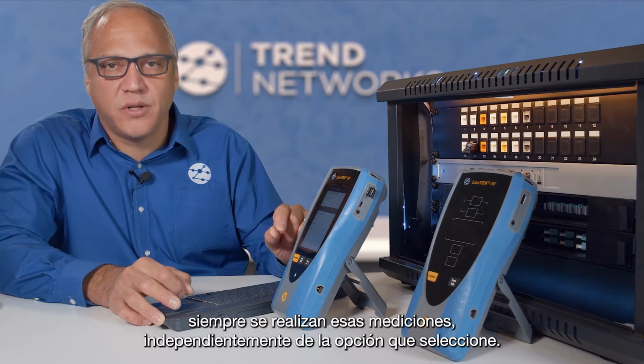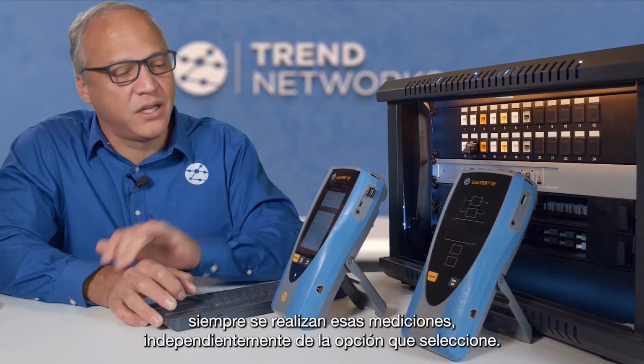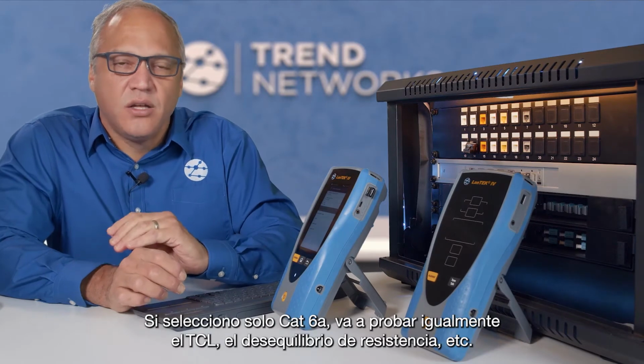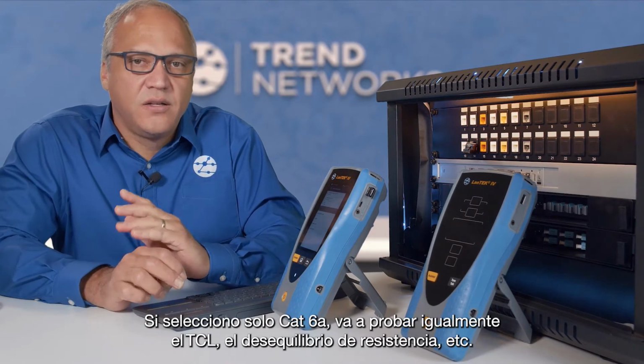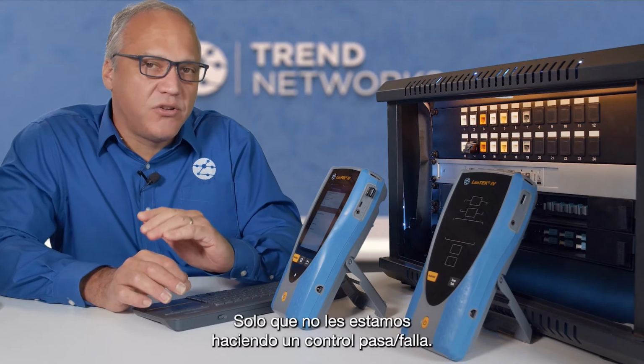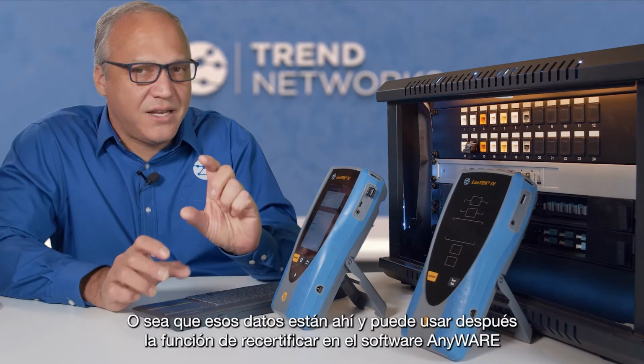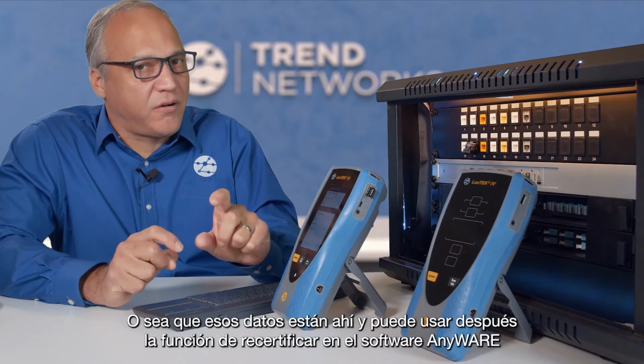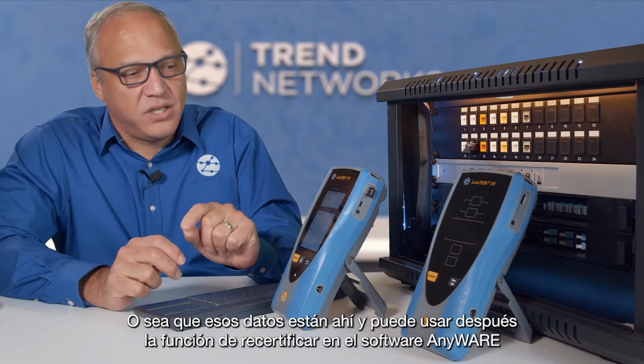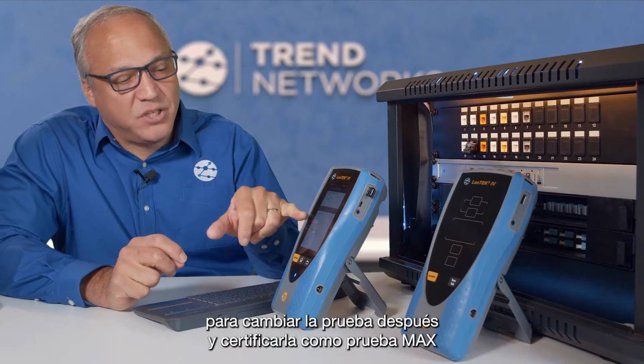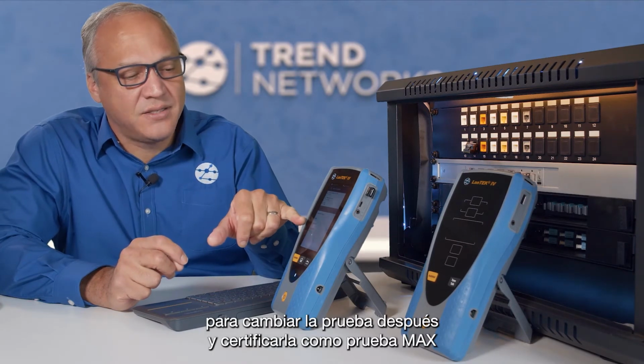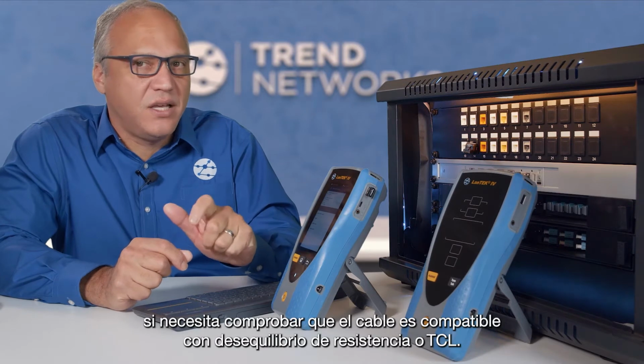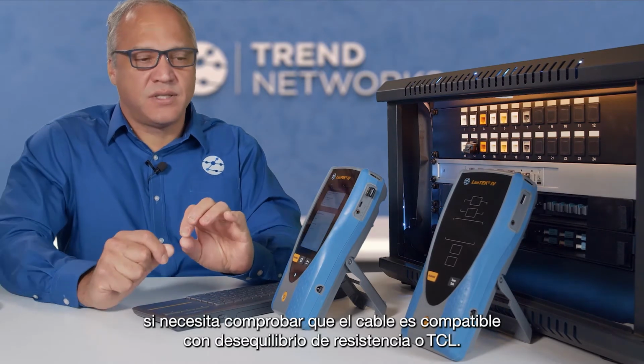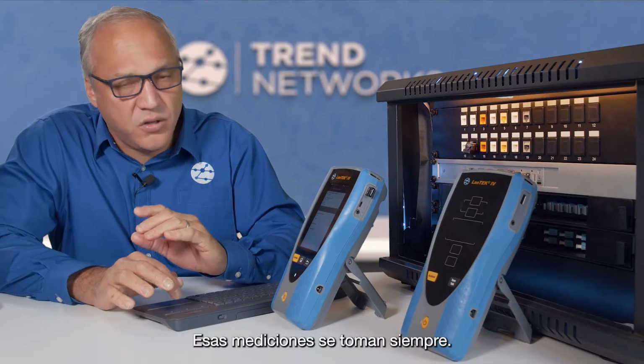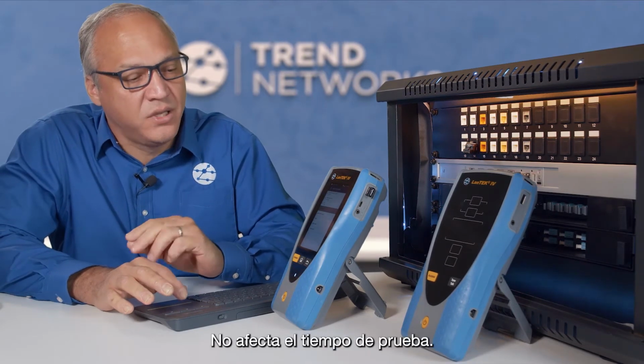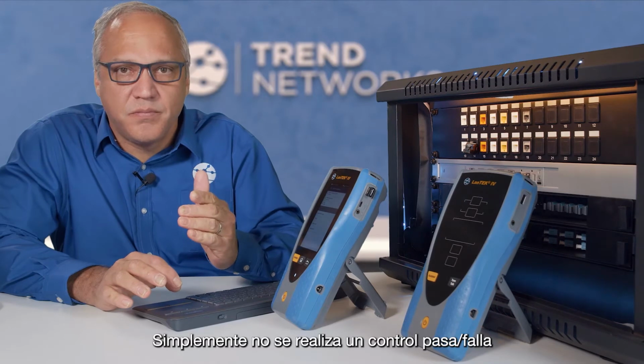We always perform those measurements regardless of which option I select. So if I select just Cat6a, we still run the TCL, resistance unbalance, and so on. You're just not doing a pass-fail check against those. So that data is there, and that lets you later on use the recertify function in the AnyWARE software to maybe change that test later and recertify it as a max test if you need to see if those cables support resistance unbalance or TCL. So those measurements are always made. It doesn't affect the test time. They're just not checked for pass-fail.